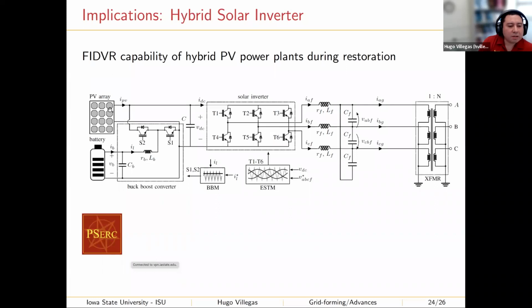And the logical part is that when we have more solar power than the solar inverter is transferring to the grid, we use that solar power to charge the battery. And when we have less solar power than the power that the solar inverter is transferring to the grid, then we use the battery to transfer that power. That is relatively simple. There is not much multi-objective optimization to do here.